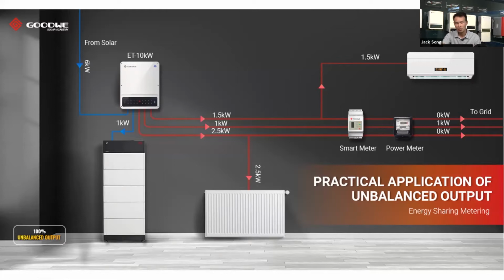Another limitation is about each phase. The output power on each phase is limited from 0 kilowatts to 33% of the nominal power of the inverter. For a 10 kilowatt inverter, each phase can output from 0 kilowatts to 3.3 kilowatts. These are the two limitations, and they are also important for the use of three-phase hybrid inverters.